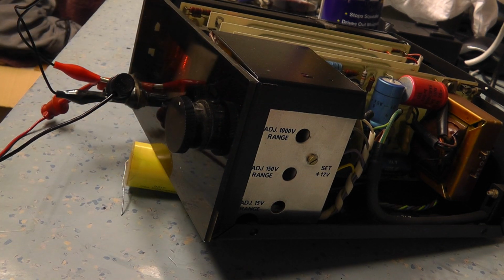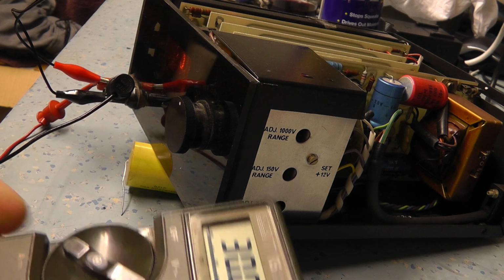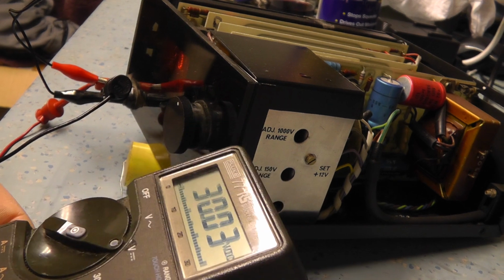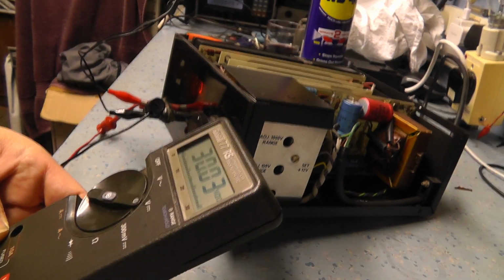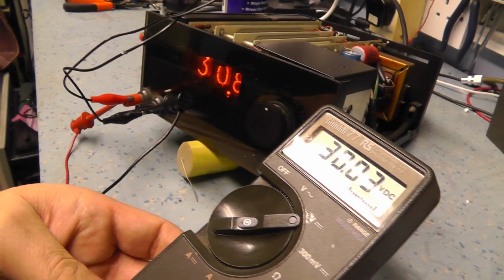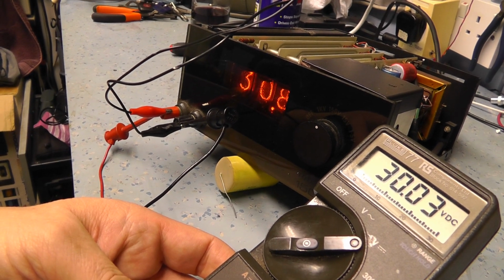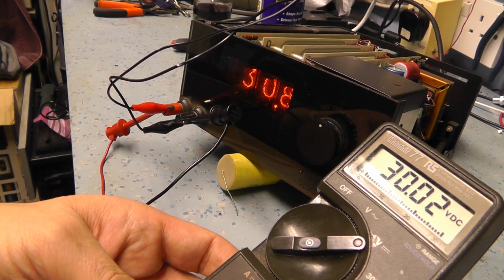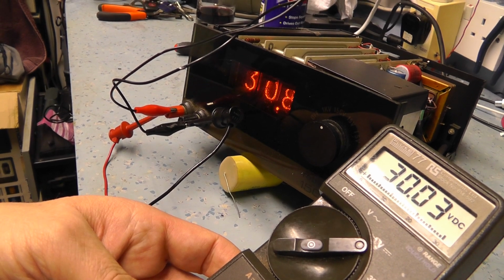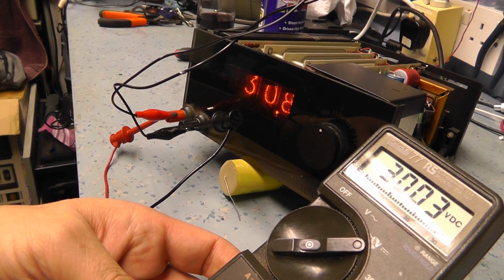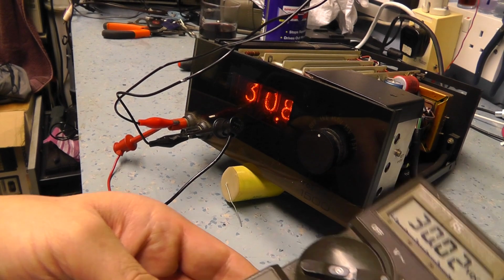So let's put it up to about 30 volts, 29 point. So my Fluke is now reading exactly 30 point. Okay, it's 30 volts, 30.03, and the Roband meter is reading... you can't see there, can you? It's reading 30.8. So it is out of spec. So let's have a look. I'm going to have a look inside, see what the adjustments are, and see if we can bring this in a bit closer into spec.